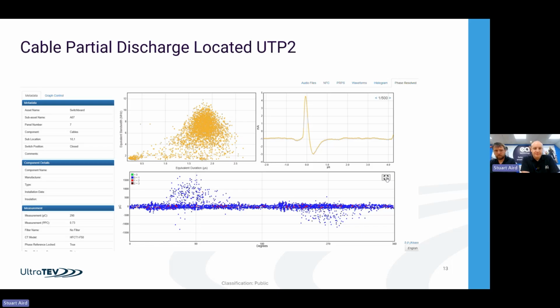So we can obviously choose the waveforms. We captured about 50 waveforms during the recording. And then we can place pointers along the route. The first one you place at your initial pulse, where the first pulse that we pick up is, and then we can put another pointer on the end of the cable circuit, and then the final one goes on the location of what we call the location pulse. So that gives us a map of the cable.